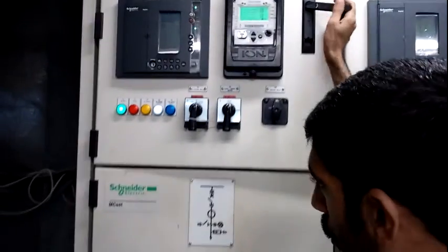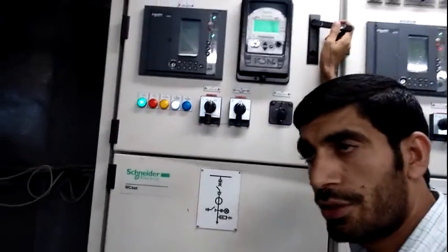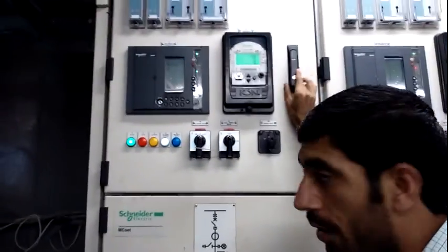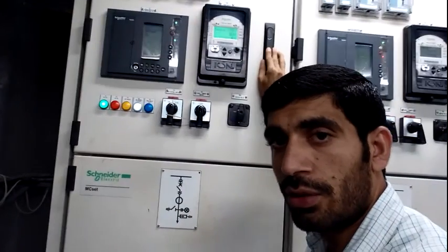These are all the components. I showed you how to operate these components, or function test, how to function test medium voltage switchgear. In two conditions, if the earth switch is closed, you cannot close the breaker. When you open the earth switch, you can close the breaker.